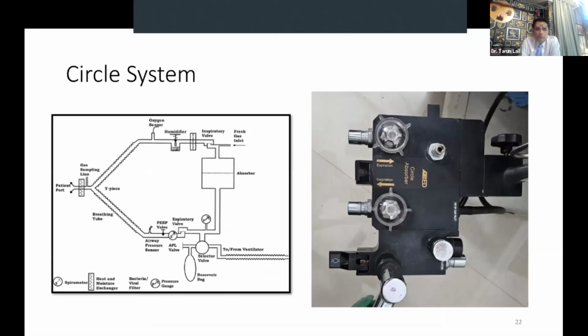Now, if we compare it to what we saw on the machine. I told you about that black tube, this is your black tube, and you can see that it has come to this place where fresh gas inlet is written. This was the diagram, and you can see that this is your fresh gas inlet. Beyond that, we had the inspiratory valve. So here we have the inspiratory valve, and this is where we will connect the circuit. Somewhere here will be your Y-piece and then the expiratory limb. So exactly as it is in this diagram, then we have the expiratory limb and the expiratory valve. So this is your expiratory unidirectional valve.